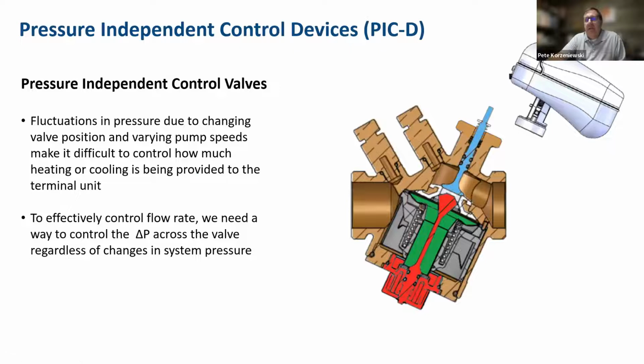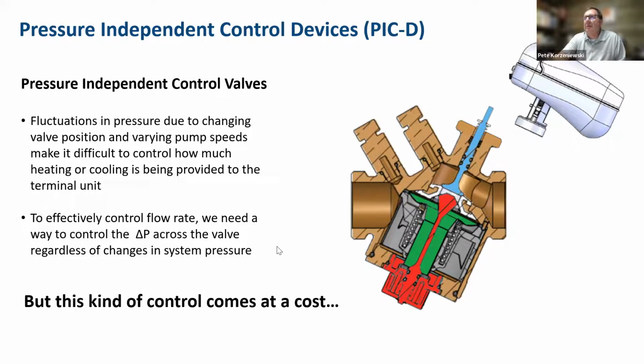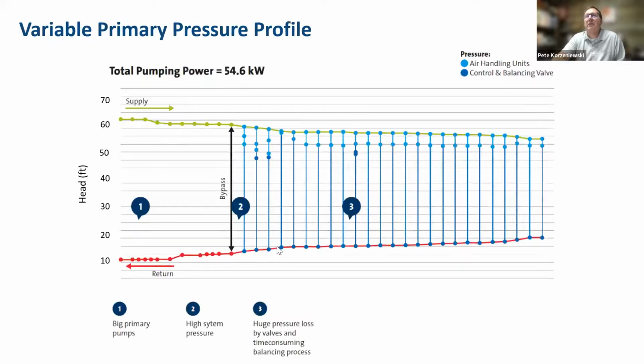So if we look closer at a pressure independent control valve, we've got that device which will eliminate those fluctuations in pressures that we see. Our top half is our actuator, which we either have as a manual setup or an automatic setup, that will open and close to allow flow into our air handling unit. And then the bottom section is a differential pressure controller that's basically going to automatically detect any changes in incoming pressure and adjust to those changes, delivering the flow that the air handling unit requires. This has been a great addition to our industry, and allowed a lot of systems to come under control and operate properly. But this kind of control comes at a cost. I don't think people think of valves as something that has a cost associated to it or an operating cost, but they do essentially use a lot of energy, and we'll talk about that.